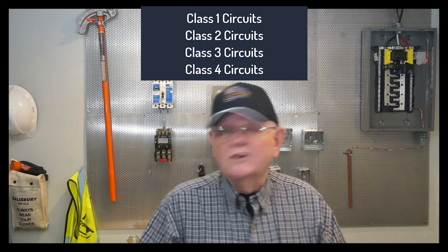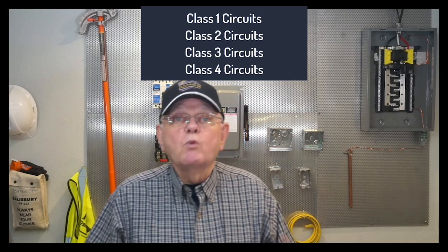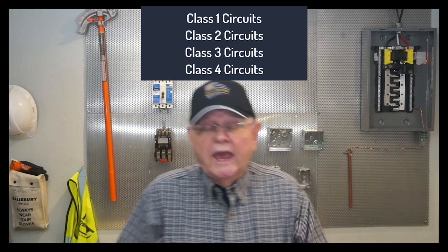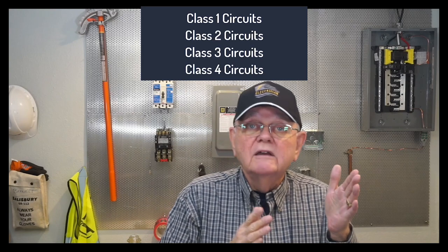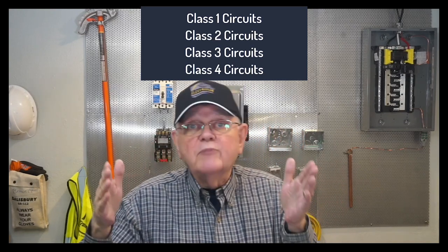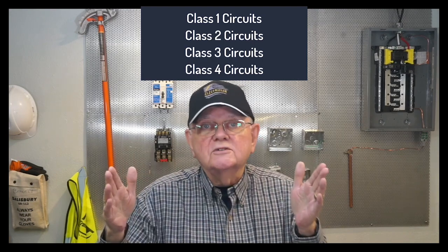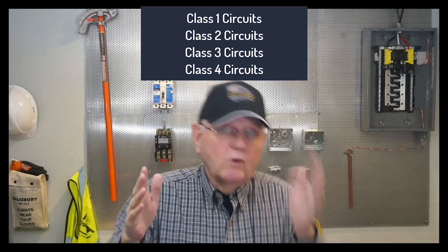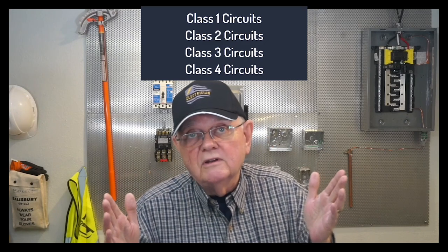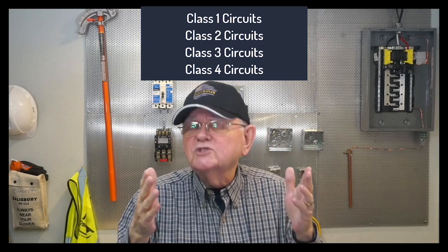There are different classes of circuits, right? We've always, for a long time anyway, had class 1, 2, and 3 circuits. And there what we have to do is look at the power supply. The conductors from the load side of the power supply out to where we utilize that power, the utilization equipment, we call those the circuit conductors. So if it's connected to a class 1 power supply, it's a class 1 circuit. We see a lot of class 2 power supplies, don't we?